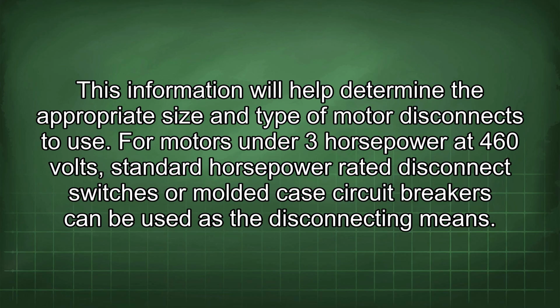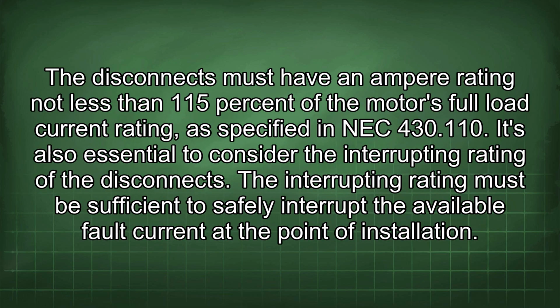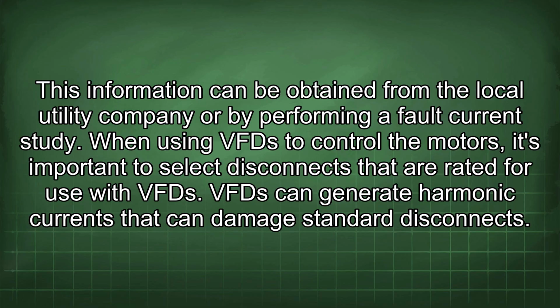For motors under 3 horsepower at 460 volts, standard horsepower rated disconnect switches or molded case circuit breakers can be used as the disconnecting means. The disconnects must have an ampere rating not less than 115% of the motor's full load current rating as specified in NEC 430.110. It's also essential to consider the interrupting rating of the disconnects. The interrupting rating must be sufficient to safely interrupt the available fault current at the point of installation. This information can be obtained from the local utility company or by performing a fault current study.